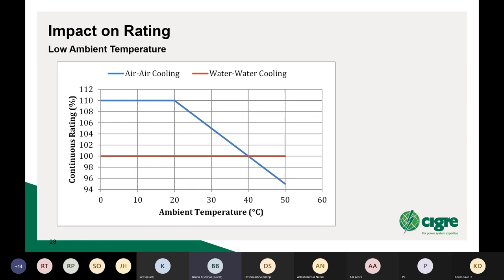So looking at the impact on rating of ambient air temperature for air-to-air cooling and water-to-water cooling, you see there's a difference. Air-to-air cooling is by far the largest, most applied technique for HVDC. And you can see that at low ambient temperature, typically you can get something like 10% extra if the ambient temperature is below a certain number, which can be specified or is typically 20 degrees C. And as you go higher than that, you typically lose some rating as the cooling efficiency declines.